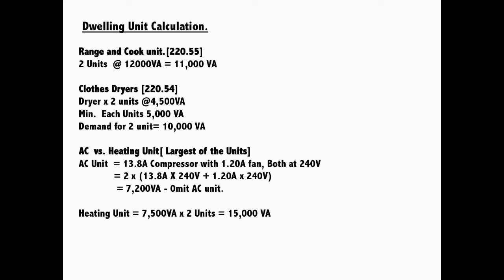For clothes dryers, according to Article 220.54, the minimum load to take into consideration is 5,000 VA. We have one unit at 4,500 VA, so we should apply the minimum requirement per demand for each dryer unit. Therefore, for two units we would have a demand of 10,000 VA.